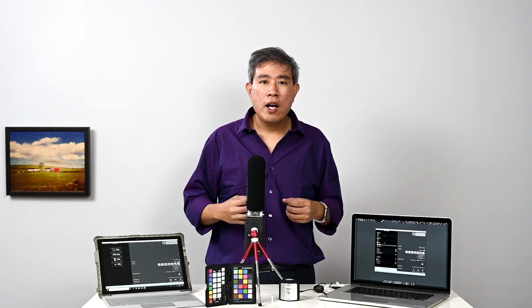The result that you're going to get out of it is a much darker photo than what you see on your screen. At that point, you're going to be wondering, what's going on? Is my calibration wrong? Have I done something wrong with that? And no, you haven't done anything incorrectly. You just didn't set the proper luminance value in that case. So in order for us to avoid those kind of issues happening, we need to set the right luminance value.